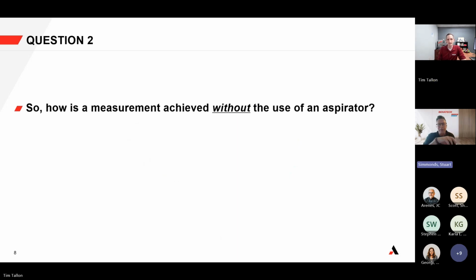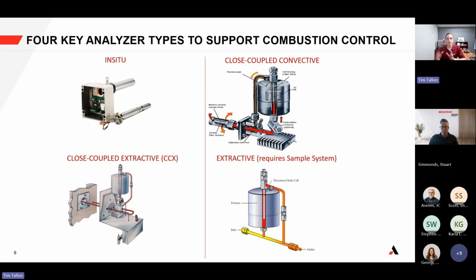That's awesome. But obviously, that's all well and good from a newbie's perspective. If you're familiar with most combustion analyzers, they're either in situ, as you say, directly in the measurement, or you're on the outside, but then you have to have some kind of motive force to get that sample out of the process and into the analyzer. So how is the HP achieving that if you're not going to use the aspirator, which is the big difference between that and every other combustion analyzer on the planet? Yeah. Aside from the question, what is an HP analyzer, this is probably the second biggest question that I get. And it comes back to almost the best of both worlds. A lot of people are familiar with the in situ type, as you mentioned. A lot of people are familiar with the close-coupled extractive type, where it has an aspirator that's pulling the sample.